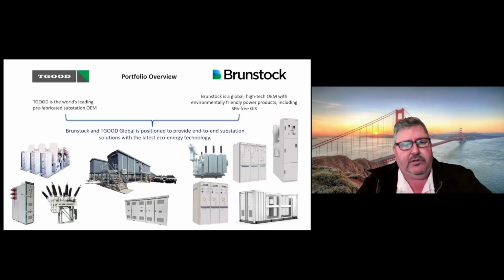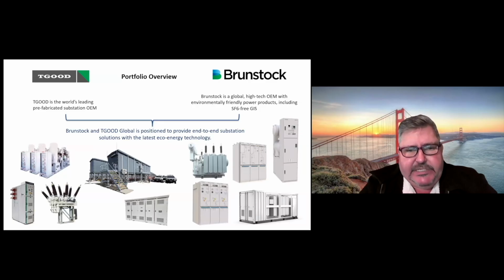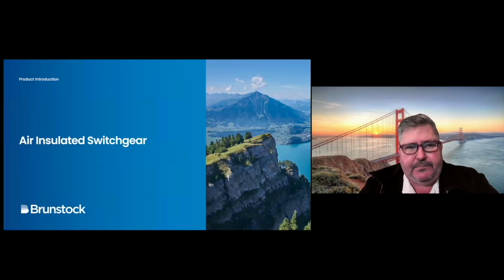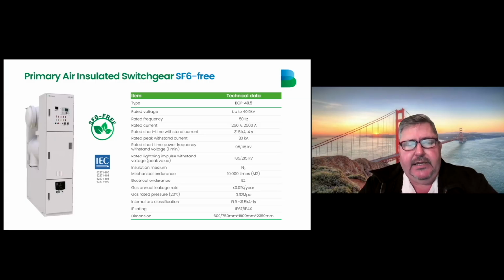In our portfolio, TGOOD specializes in prefabricated substations, where it's much easier to transport the equipment to site after the whole substation has been built, making it faster for the renewable industry to keep up and running and also improve their production cost. On our air-insulated switchgear, the new range that TGOOD has brought out, we can offer up to 40.5 kV air-insulated switchgear rated at 2,500 amps, 31.5 kA.